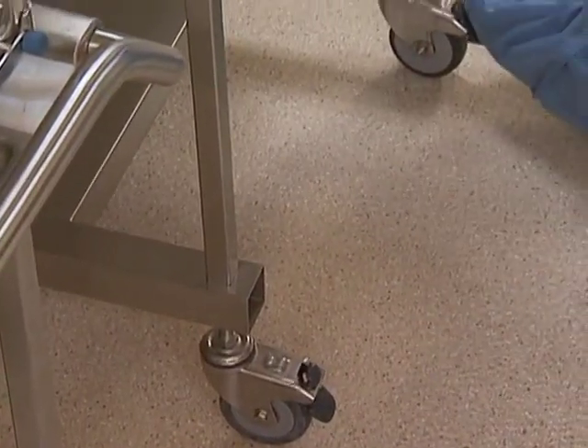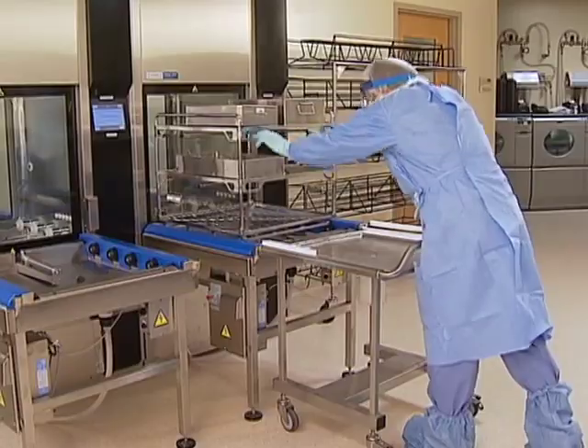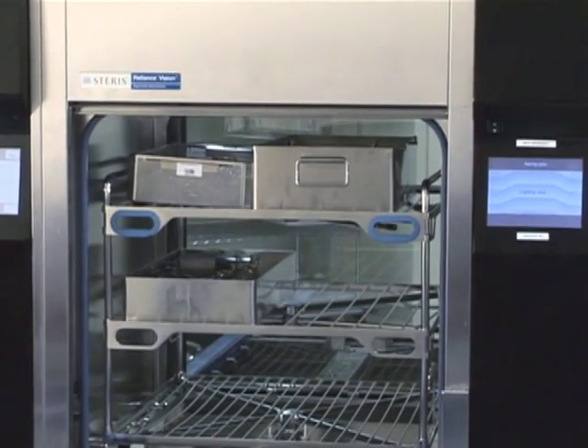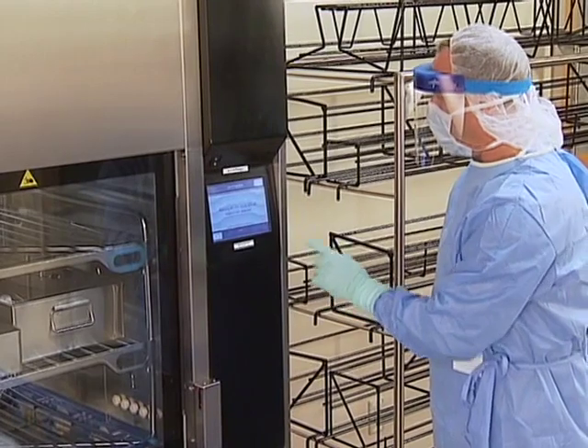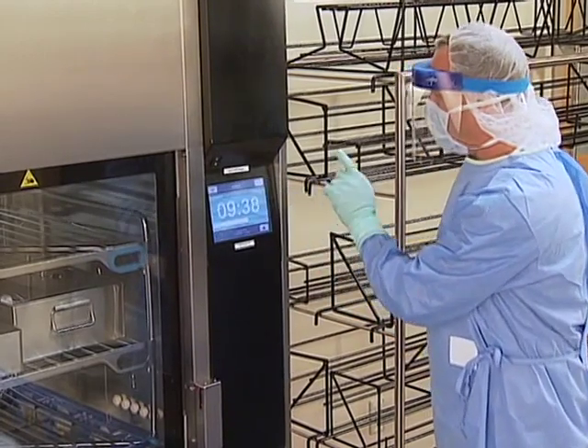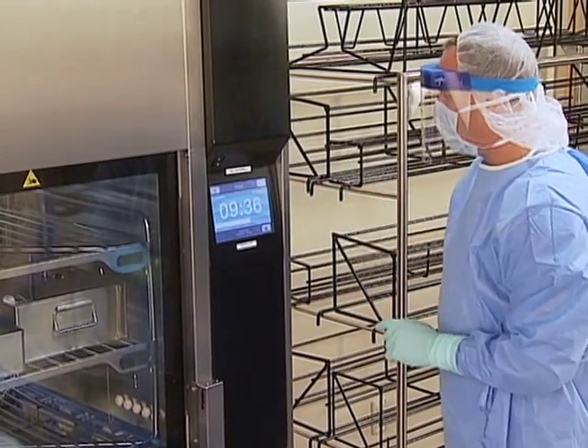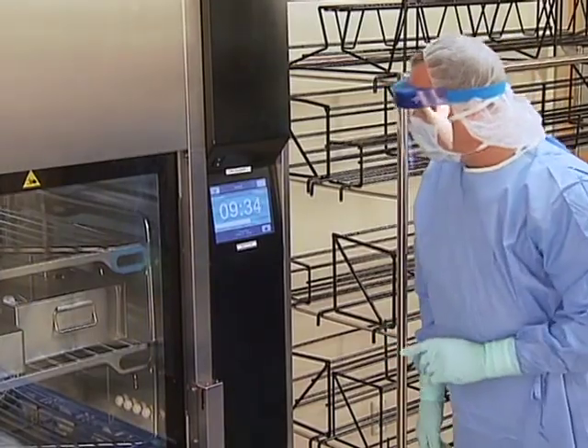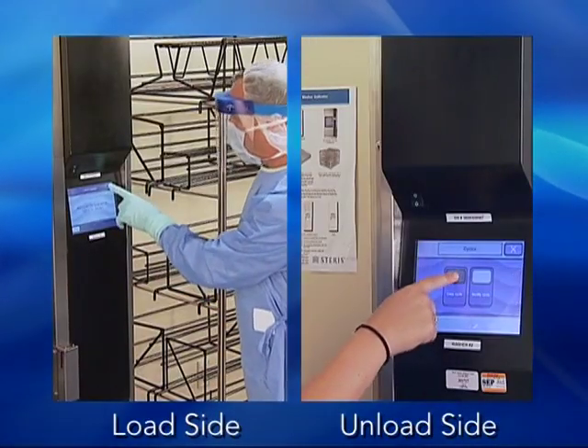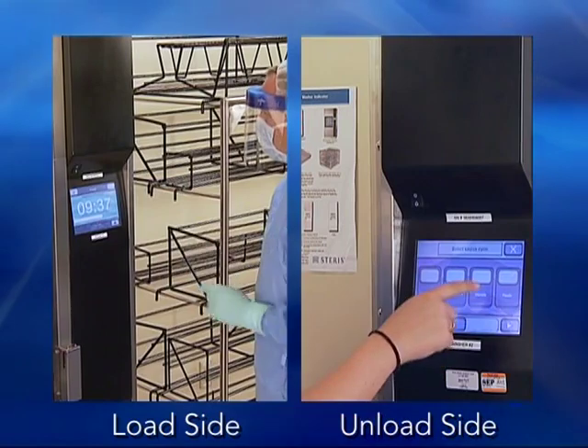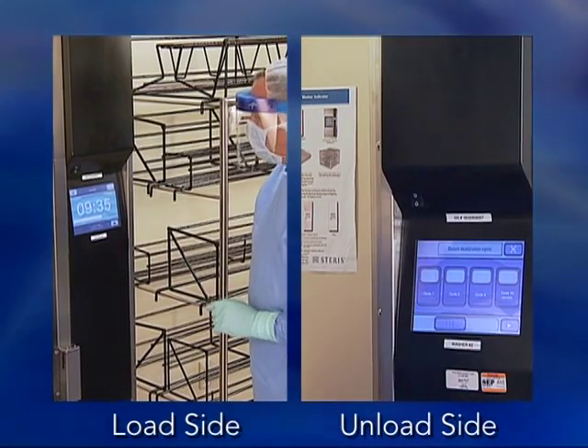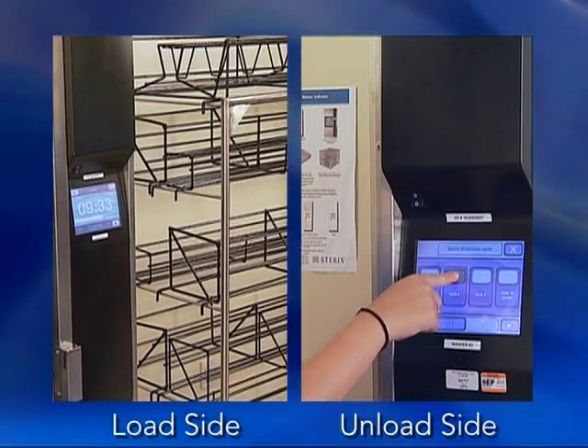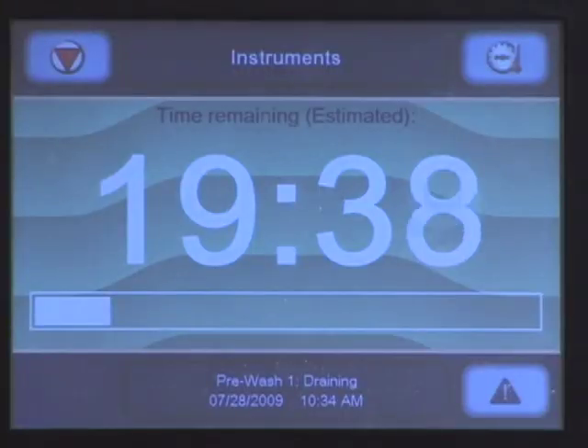Lock the transfer cart into place and carefully load the rack into the chamber. Now you're ready to initiate the cycle. Our PC Control touchscreen and pre-programmed cycles make it easy to start a cycle and track its progress. The Vision single-chamber washer is equipped with two PC Control System touchscreens, one on the load side and the other on the unload side. Identical information is displayed on both touchscreens.